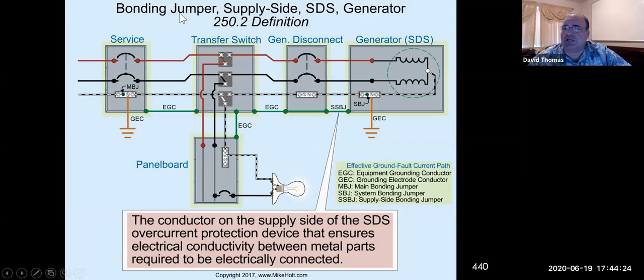And so now we're going to look at the bonding jumper here, supply side, but in this case it's a generator. The idea is that we have dual sources here. This is actually a pretty typical installation for a hospital, for many places that actually have a generator backup system. And you don't want to, if you lose power from the main service, so let's say you're going to have the utility over here. This is the utility here. So this would be PG&E over here. And then you have a generator here, and we have a transfer switch in the middle.